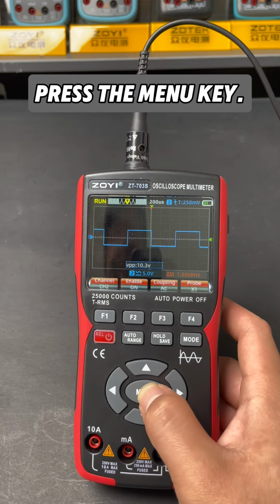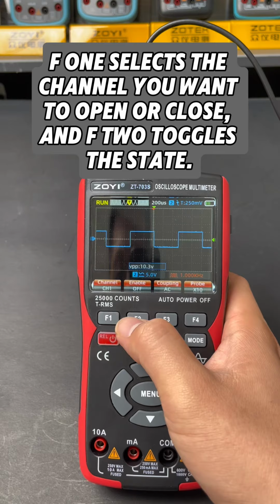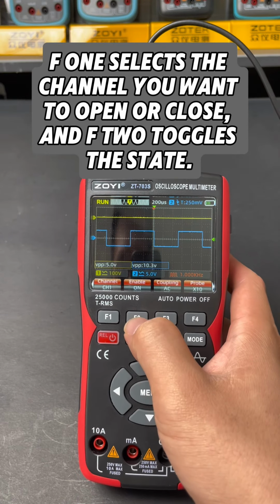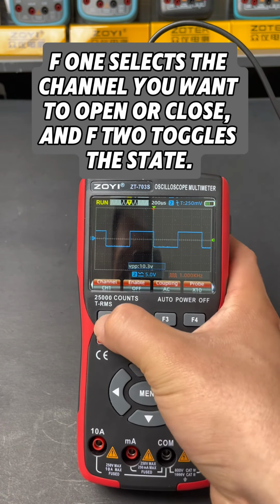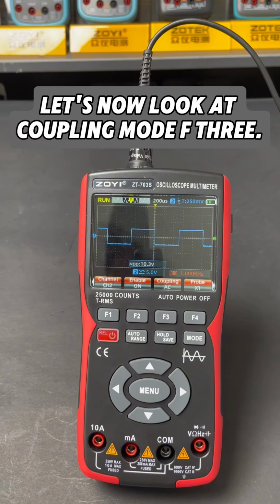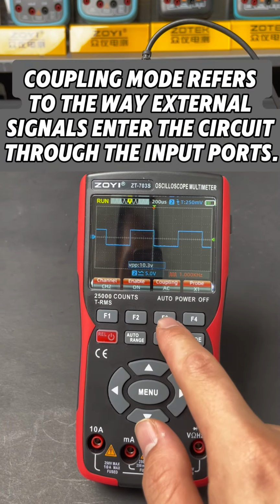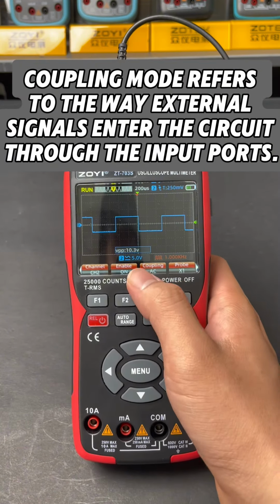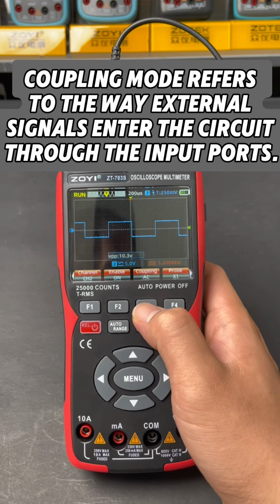Press the menu key. F1 selects the channel you want to open or close, and F2 toggles the state. Let's now look at coupling mode F3. Coupling mode refers to the way external signals enter the circuit through the input ports.